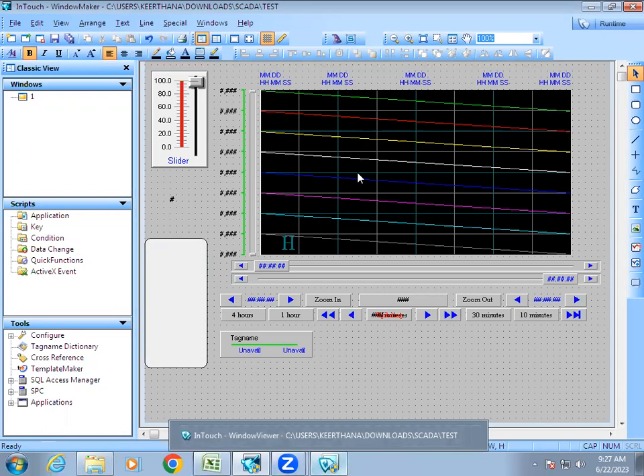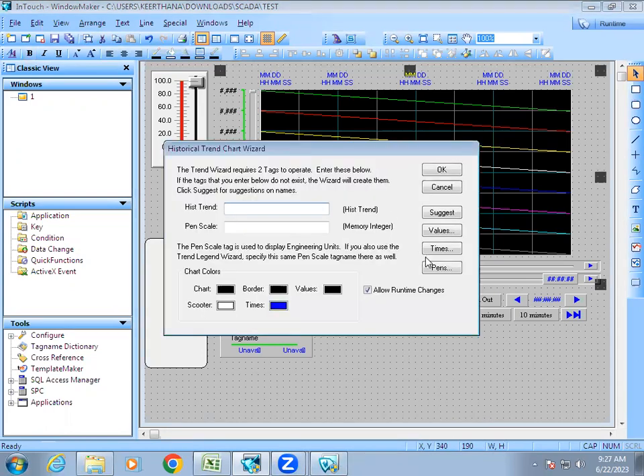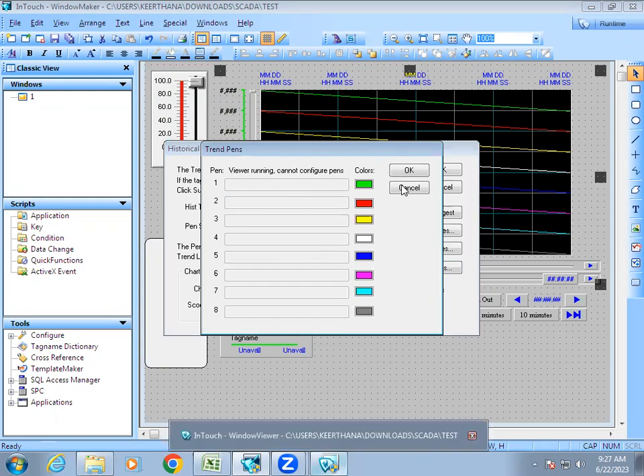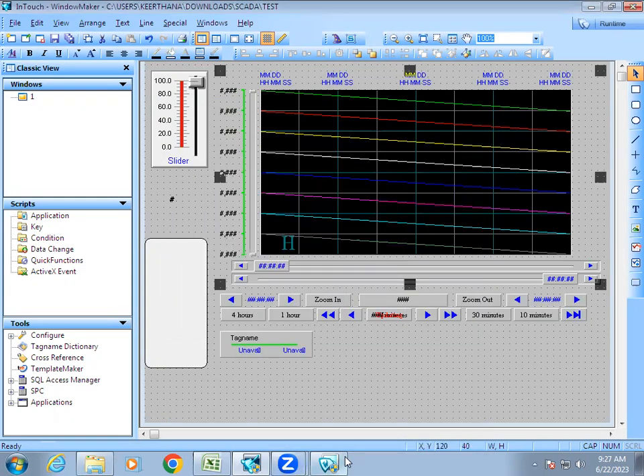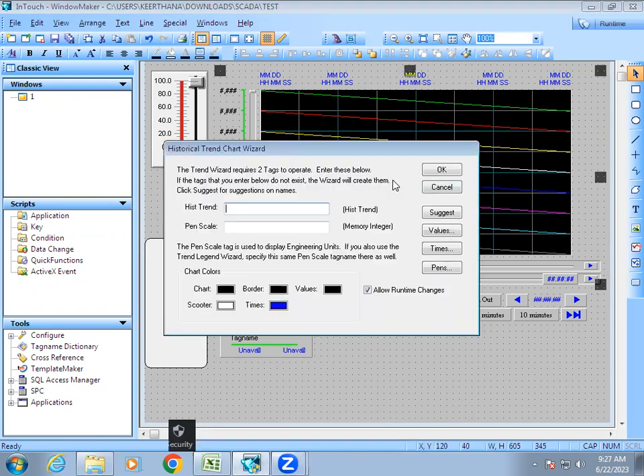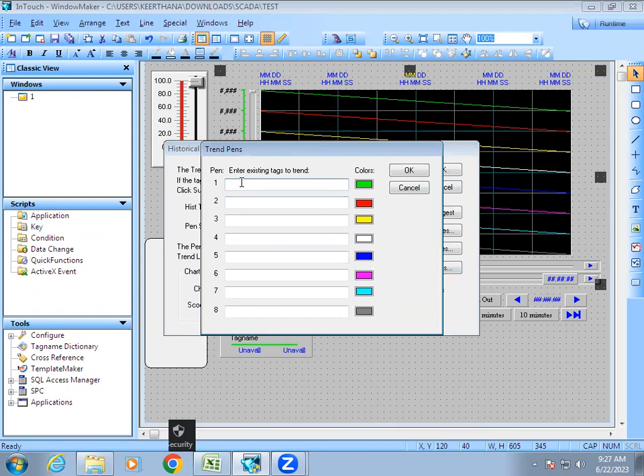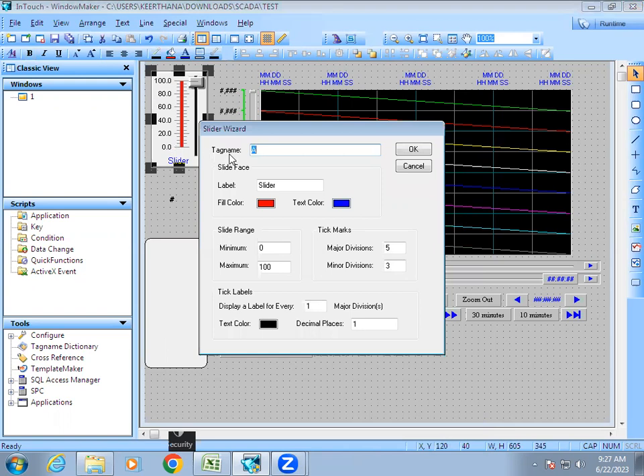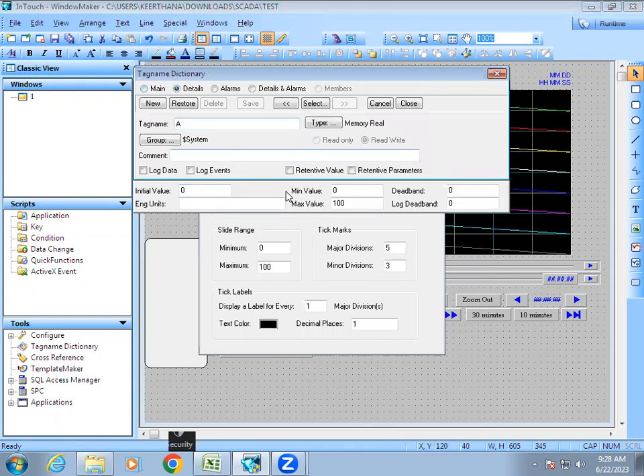When setting up the historical trend, first close the window viewer runtime window. Then double-click the chart and go to Pen to assign the tag name. While the window viewer is open it won't allow changes, so close it first. When you double-click the pen it is not showing our tag name yet, because for past data we need to make a change in the tag — specifically, we need to enable 'Log Data' in the tag name dictionary.